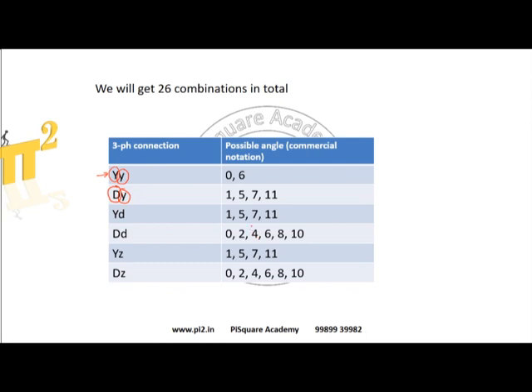So here, YY0 and YY6. YY0 means the angle between the high voltage and low voltage winding is 0 degrees — or in clock rotation, 12 o'clock. YY6 means star-star with 6, which means 180 degrees. Here we can get two different combinations.